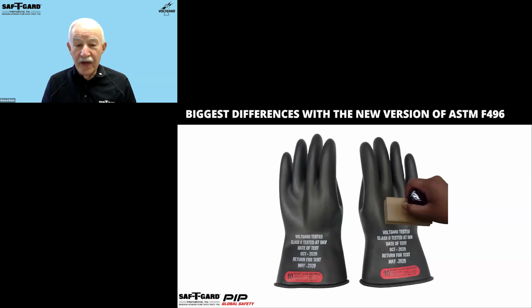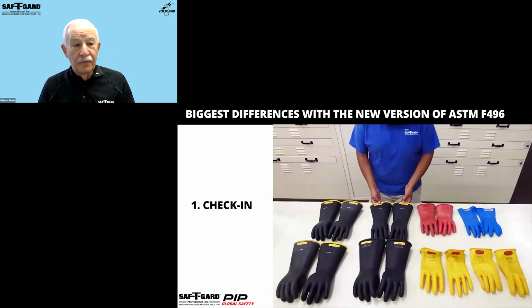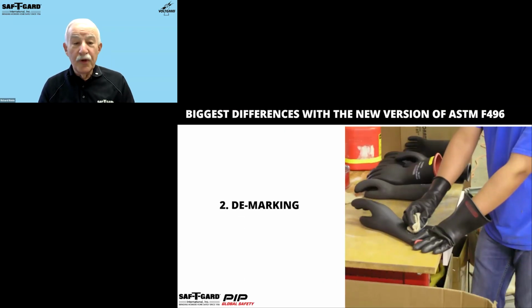In our experience, we recommend a more effective way to manage that in-service time period is for the electrical testing facility to mark the next return-for-test date according to company policy and within that OSHA-mandated ASTM in-service time frame. If you do not have the equipment required to perform these electrical tests, there are independent test facilities that can perform the acceptance test and in-service testing on behalf of end users. At a minimum, ASTM standards require that the inspection and procedure follow this sequence. First of all, they need to be checked in. They need to be demarked to remove any previous test marking.